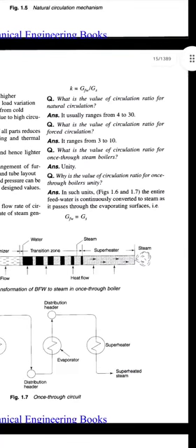What is the value of circulation ratio for natural circulation? It usually ranges from 4 to 30. What is the value of circulation ratio for forced circulation? It is 3 to 10. What is the value of circulation ratio for once-through steam boilers? It is unity.